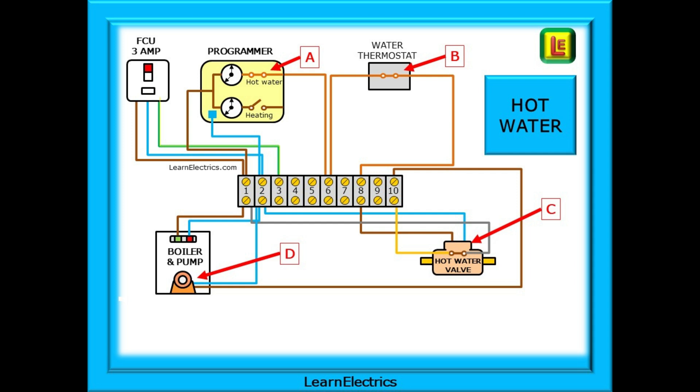As the valve opens, it closes a microswitch inside the valve body. The grey wire at the valve is a permanent 230 volts taken from terminal number 1. With the switch closed, the voltage passes through to the orange wire and travels to terminal number 10. From number 10, 230 volts travels to the pump motor at D and the pump turns on. Because the valve is now open, water will flow around the hot water system.